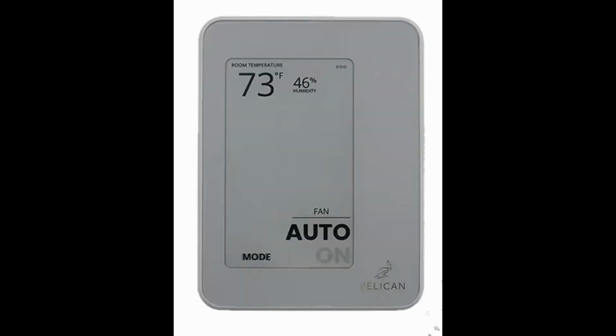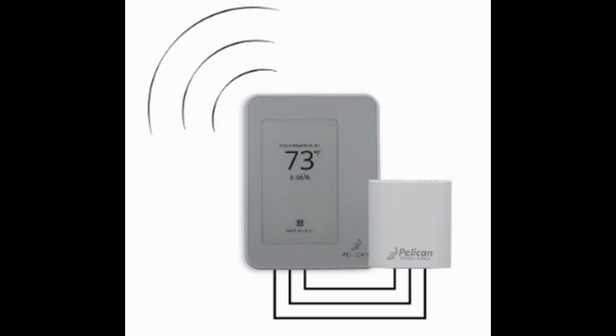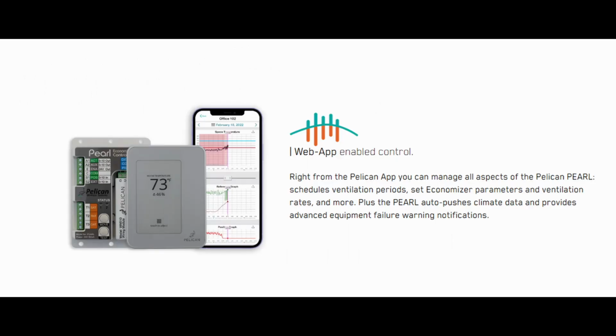The Pelican TC1 thermostat can be wired and configured to handle either type of unit. You will also want a Pelican TA1 and T1 duct probe to measure and report the supply air temperature. If the unit has an economizer, you will need a Pelican Pearl in place of the TA1 to control the economizer damper based on outdoor air conditions. The Pearl comes with required sensors needed for supply air, return air, and outdoor air temperature measurement, and can be configured to control the economizer to your specifications using the Pelican web interface.